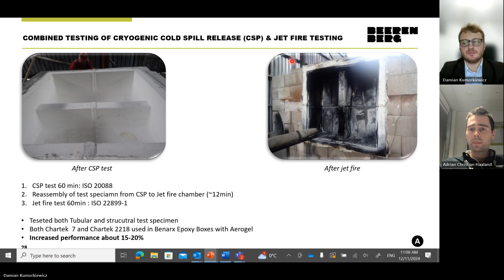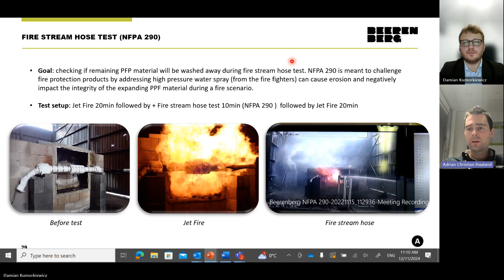It's always fun to test new standards, new improvements in the industry coming out. A couple of years ago, we tested a fire stream hose standard called NFPA 290, and it's designed to challenge what happens to the ongoing performance of the system if it's subjected to high pressure water hose impact from, for example, firefighters or water cannons or deluge, etc. Because this can cause a lot of thermal shock to the system and also have an erosion effect on certain types of PFP. How the standard works, you do 20 minutes of jet fire, then you subject it to 10 minutes of water pressure, and then you follow on by doing a subsequent 20 minutes of jet fire testing to see that it can meet 50 minutes in total and provide the same duration to 400 degrees critical that it does originally.